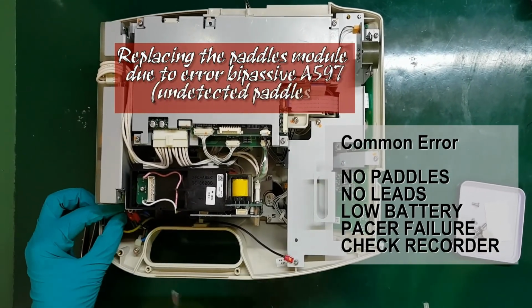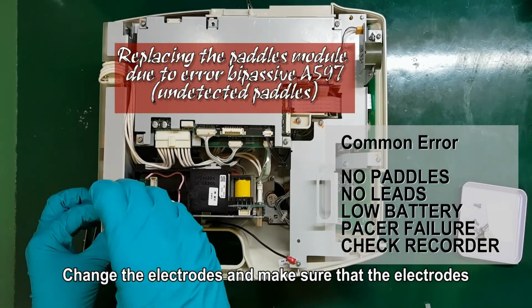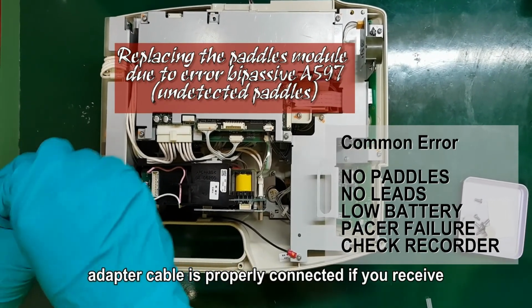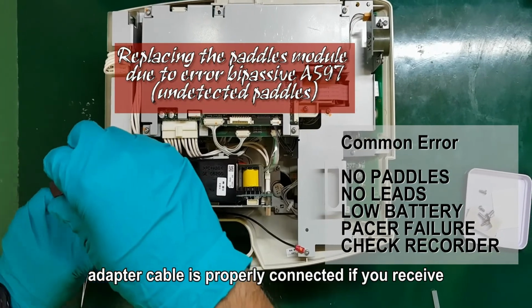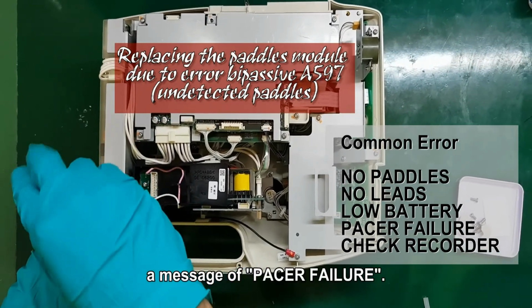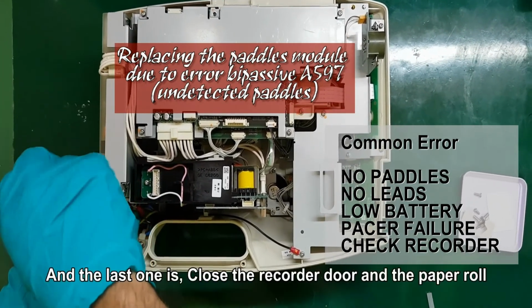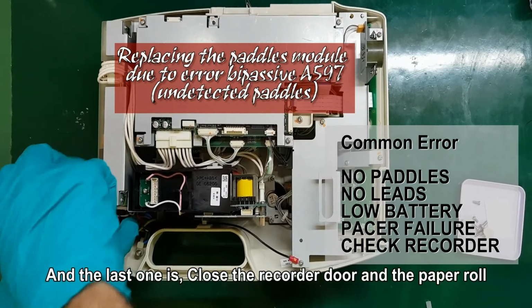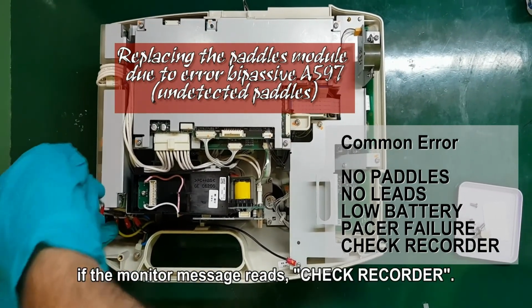Change the electrodes and make sure that the electrodes adapter cable is properly connected if you receive a message of pacer failure. Restart the pacer. And the last one is close the recorder door and the paper roll if the monitor message reads check recorder.